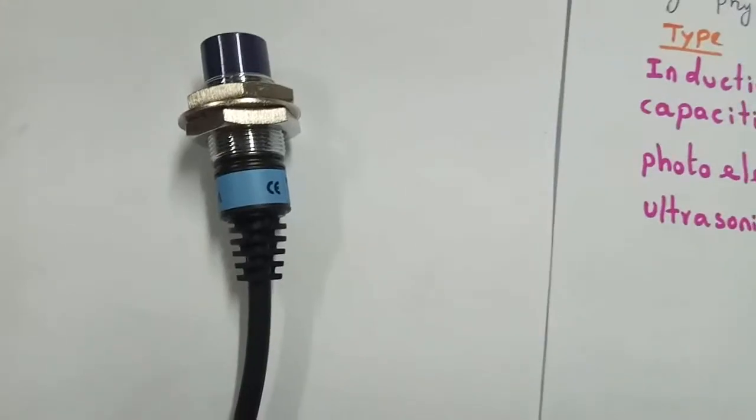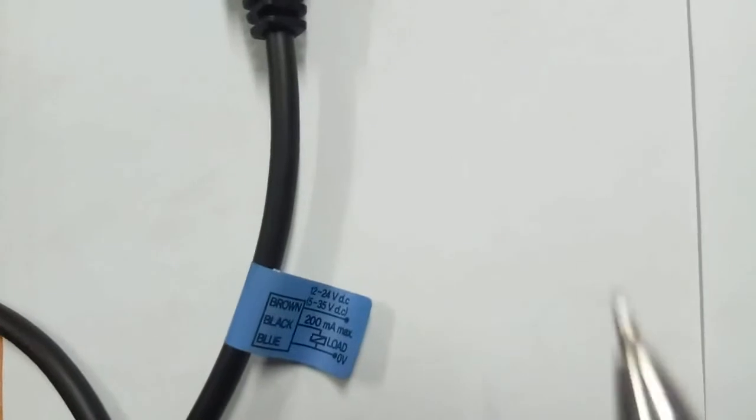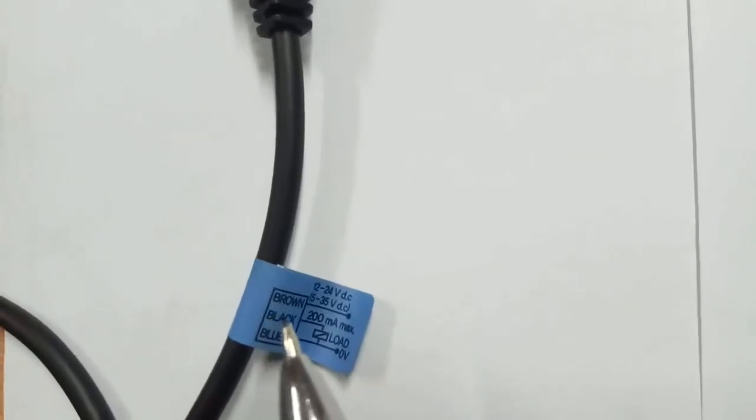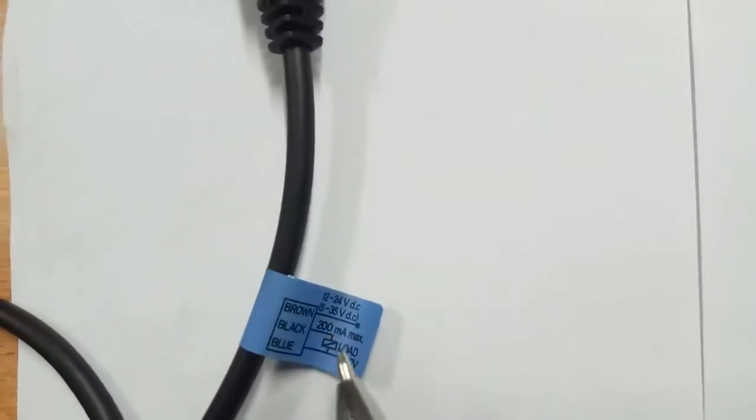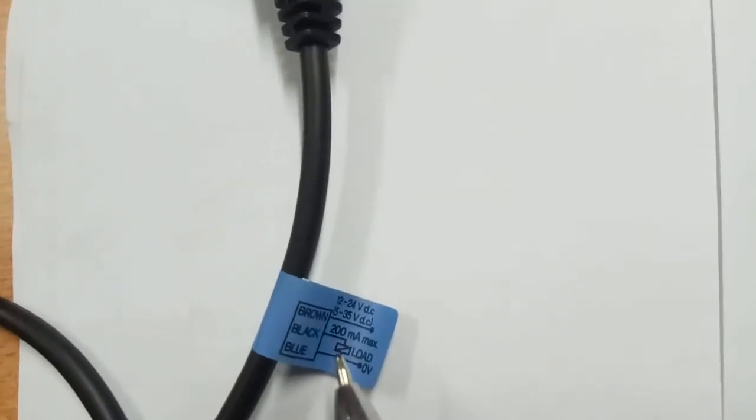This is the inductive Proximity Sensor. Black, blue, brown wire. Brown is positive, blue will be 24V DC negative, black is output. This should allow relay or PLC module. So you can allow it to get the connection.